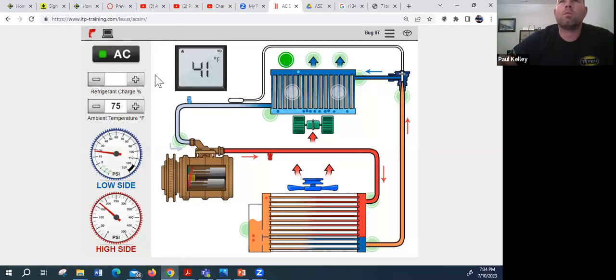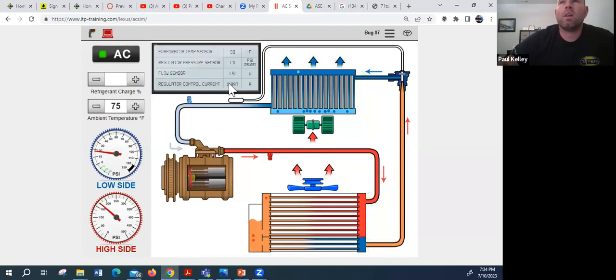So we've got a few things we can do. Because this has a variable compressor, if we look right here, it's got 0.997 amps, almost 1 amp, that's maximum stroke. Now, if you look, our low is already too low, so why are we still doing maximum stroke? We must be getting some bad input. What other inputs can we see here?